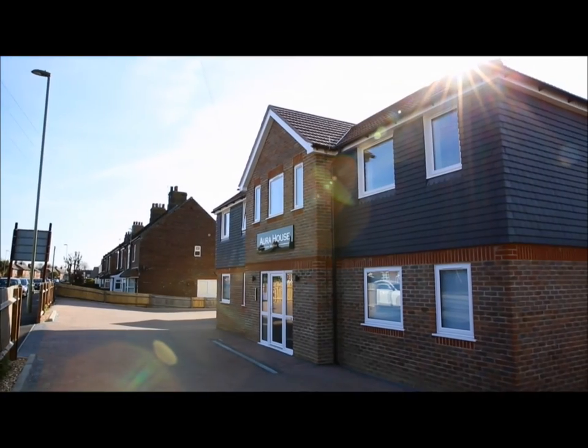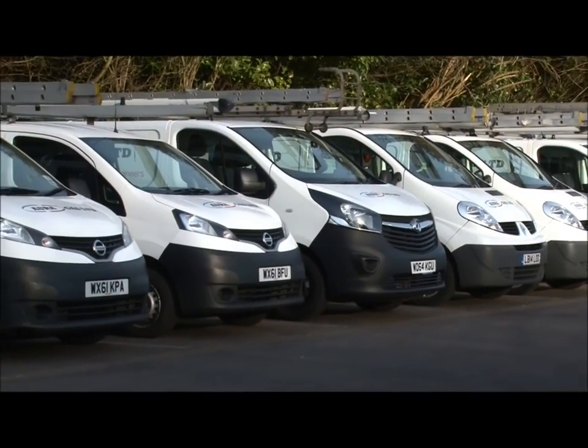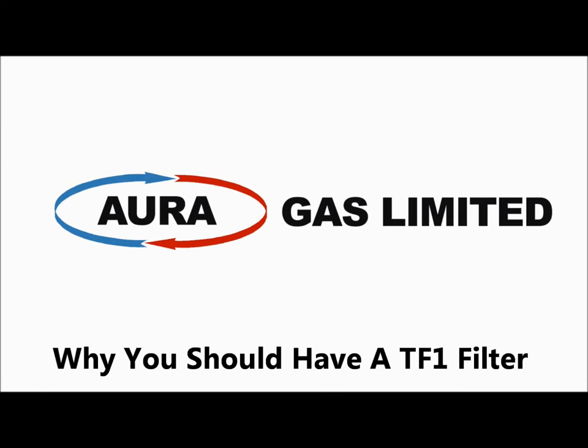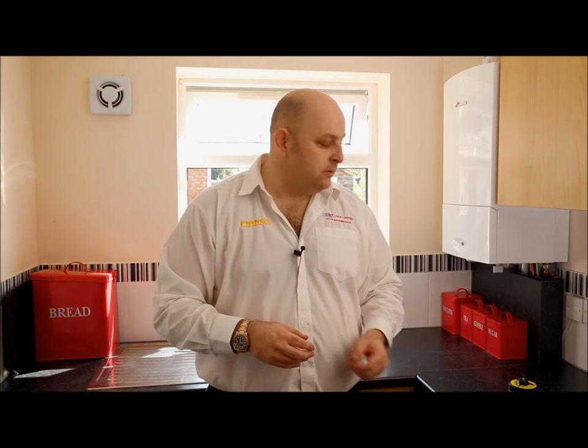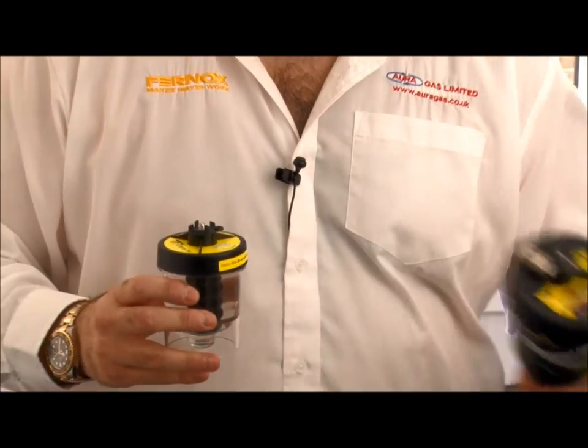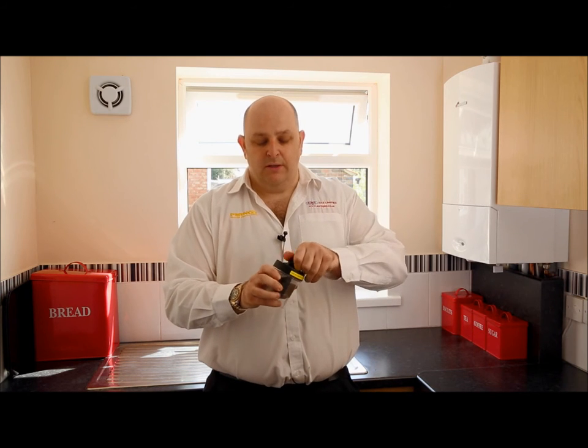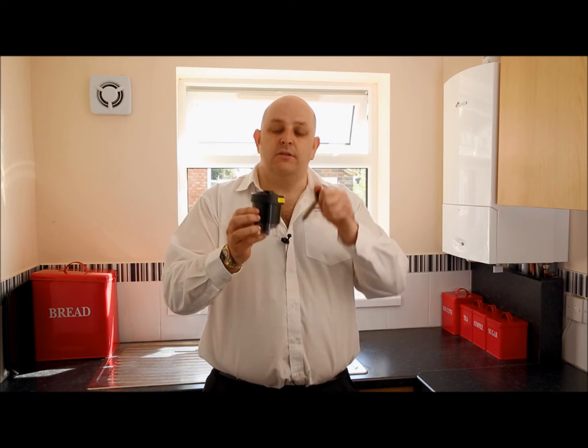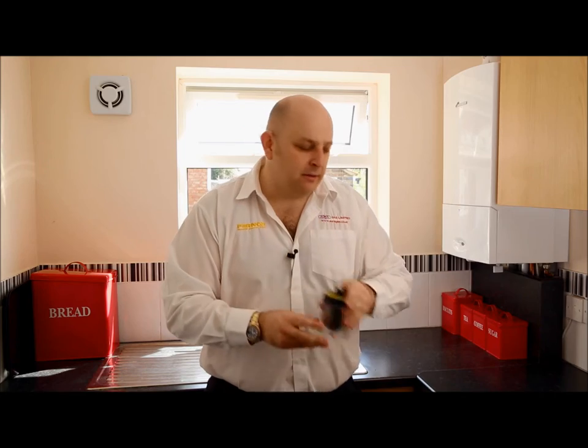We've worked very closely with AuraGas over the years — 10 plus years — and we've helped train all of the AuraGas engineers. New boilers are a lot more susceptible to sludge and what we call magnetite, so it's important to try and protect the boiler against this by using a filter. We fit Fernox TF1 filters to prevent that. The magnetite in your existing system is collected within the filter and gathers around a big magnet. The downside of these filters is they're quite ugly to look at.